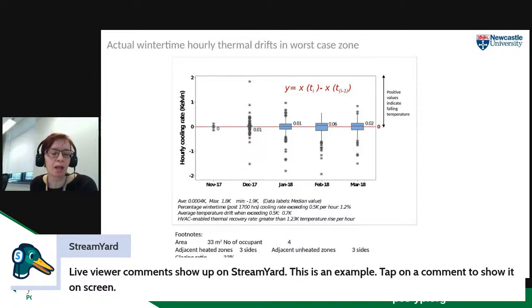So again, modelling the building, looking at winter time, we looked at 5 heating months in the UK. Sadly, there's more than 5, but anyway, we looked at these 5. And we looked at, if we turn the heating off, turn off the heat pumps, turn off the circulating pumps, how quickly does the space cool down? How quickly do we have to then turn it back on again in order to keep comfort to an appropriate level? So the building set point is 21 degrees for heating. And thermal comfort standards produced by the industry say a thermal drift, i.e. temperature change, of no more than 0.5 degree per hour in order for comfort conditions to be maintained. So it's not just how much it cools to, but how quickly it cools that matters.